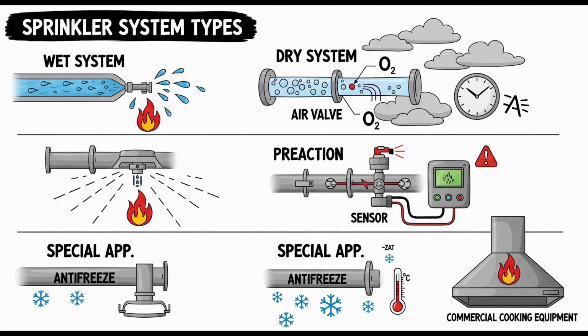And just like with dry pipe systems, a listed quick opening device, QOD, is permitted to help meet the timed or calculated requirements for double interlock systems by speeding up the main valve trip when both conditions are met. Got it. Supervision is also mentioned for pre-action systems with more than 20 sprinklers. What needs supervising? If a pre-action system has more than 20 sprinklers, both the sprinkler piping network itself and the fire detection devices must be automatically supervised.